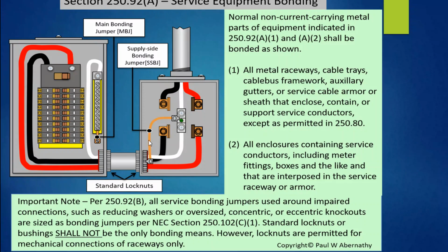Now, here's the thing. I lean towards it being over here in the service equipment. Why? Even though the code permits it over here, once this is all done and I sign off on it and the utility comes to energize it, they might not like it and they might rip it out. If they rip it out, then I, as an installer, might not be coming back to this job, so I might not know that there's one in it. That means this nipple becomes isolated and has to rely on these eccentric and concentric or impaired connections, and we don't want to rely on that when we need to make sure it makes that connection. Remember, there's no overcurrent protective device ahead of it that we're aware of, so we're going on a leap of faith that the utility has one on the primary side. So we want to make sure these connections are done properly. So I like it over here, but the code does permit it over here.